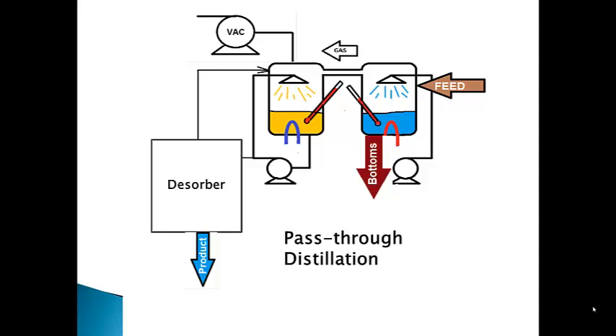Now I would like to share with you the contribution that Drystill has made to the field of pass-through distillation. Here is a block diagram of pass-through distillation with the evaporator and the absorber shown as 2 separate vessels connected by a vapor duct. But since the 2 vessels operate at the same pressure, they may be combined into a single shell. Manufacturers of absorption chillers do exactly that.